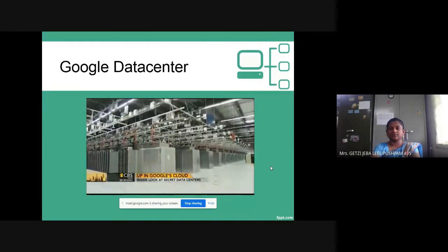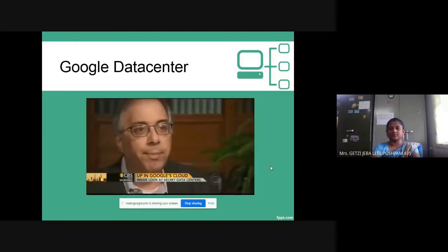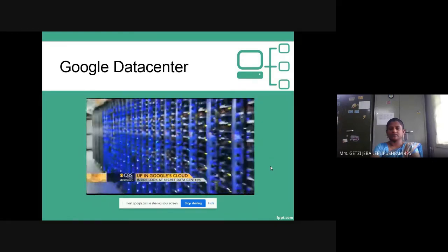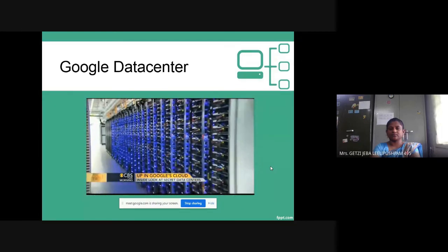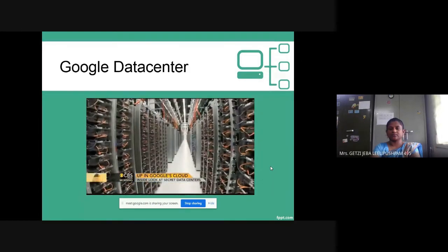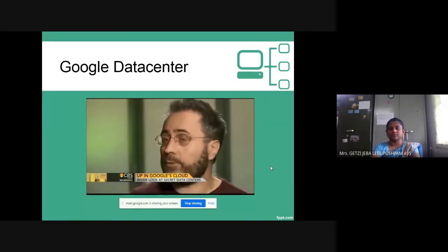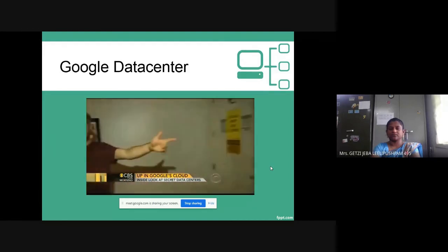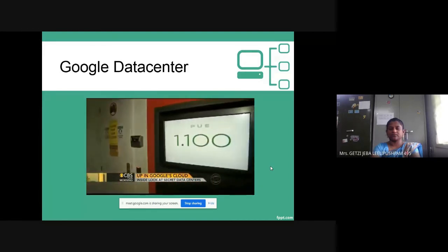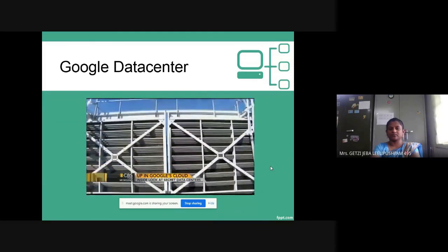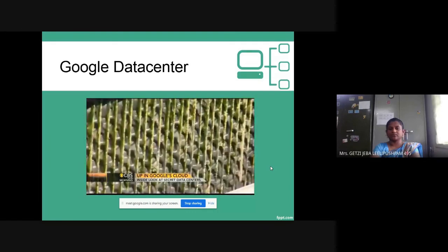The opening up of data centers really comes from their feeling that they can't keep this themselves. Google reduced a lot of its energy consumption by simply raising the temperature on the server floor from a chilly 68 degrees to a balmy 80. We're estimating that we saved over $1 billion in the history of Google through these efficiency measures. At Lenoir, Google says only 10% of the electricity is not used to power its servers. Another Google innovation, replacing wasteful air conditioners with a water-based cooling system.